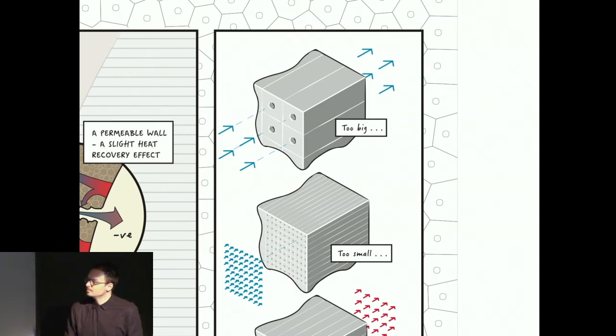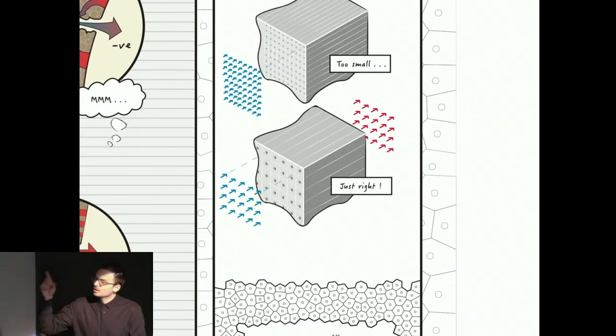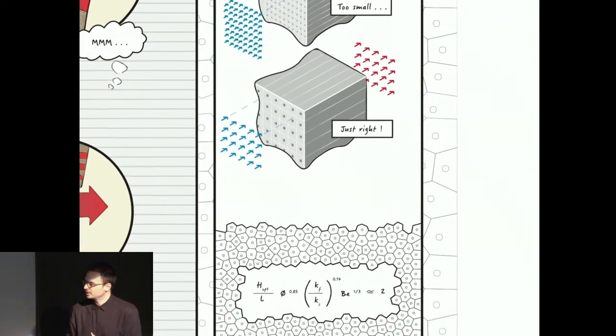If the holes are too big, the air won't have enough contact with the material to be pre-warmed sufficiently. If the holes are too small, you'd get a lot of heat recovery, but you'd have a very large pressure differential to overcome, so you'd need a very large fan to suck through the air, or a huge chimney to pull it through by buoyancy ventilation. But there's a moment where it's just right, where given a fixed pressure differential and how much heat you want to recover, and the material you're working with, you can optimize the pores and get the desired amount of heat recovery.